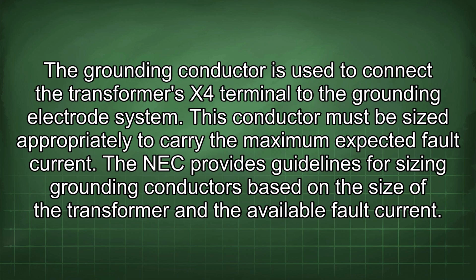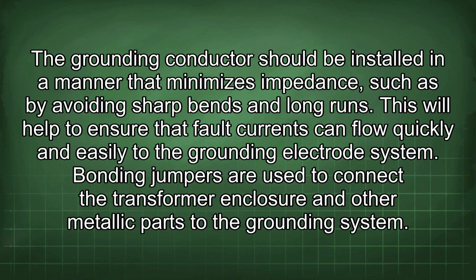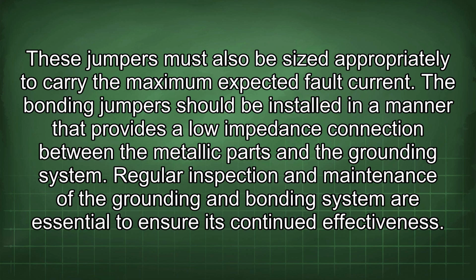The grounding conductor is used to connect the transformer's X4 terminal to the grounding electrode system. This conductor must be sized appropriately to carry the maximum expected fault current. The NEC provides guidelines for sizing grounding conductors based on the size of the transformer and the available fault current. The grounding conductor should be installed in a manner that minimizes impedance, such as by avoiding sharp bends and long runs. This will help to ensure that fault currents can flow quickly and easily to the grounding electrode system. Bonding jumpers are used to connect the transformer enclosure and other metallic parts to the grounding system. These jumpers must also be sized appropriately to carry the maximum expected fault current. The bonding jumpers should be installed in a manner that provides a low impedance connection between the metallic parts and the grounding system.